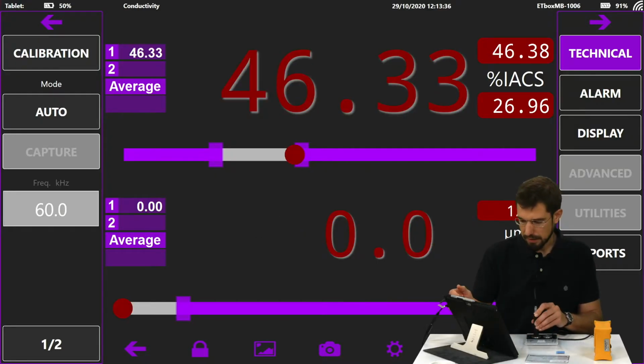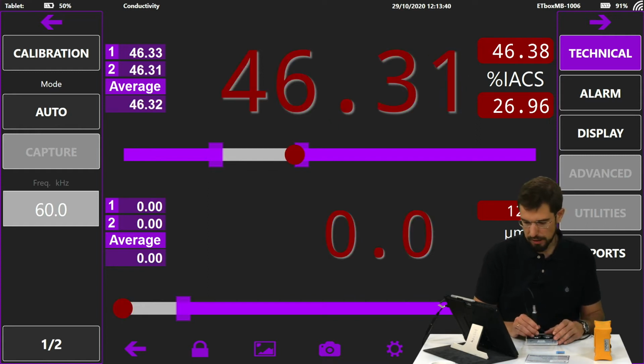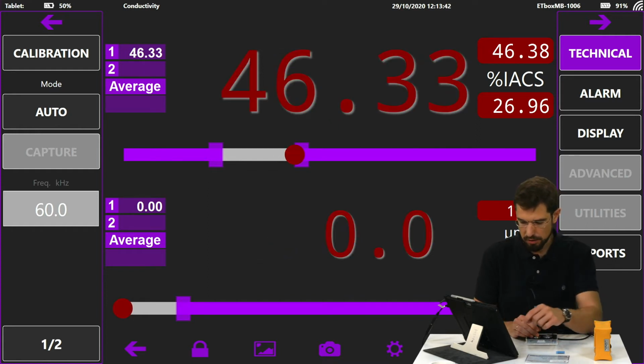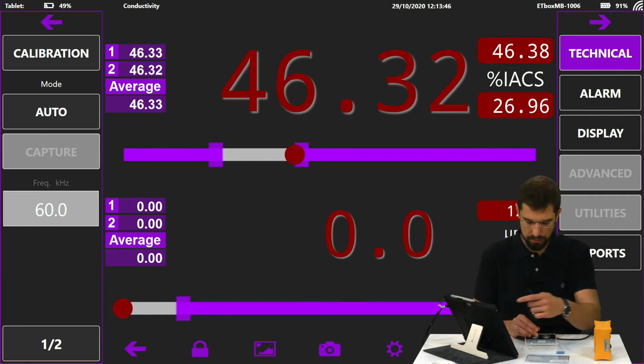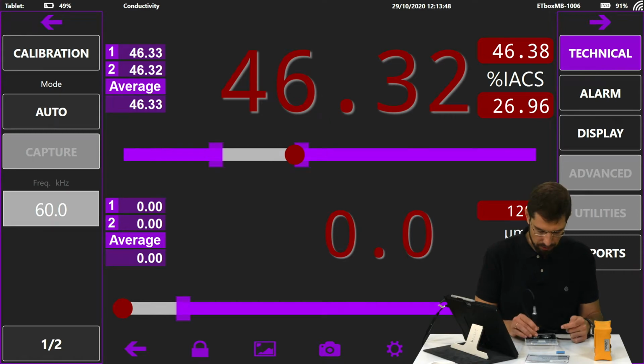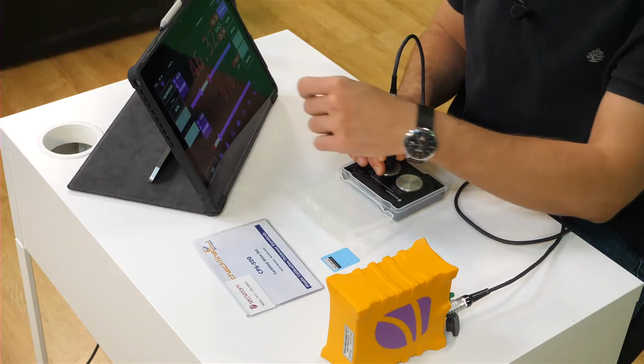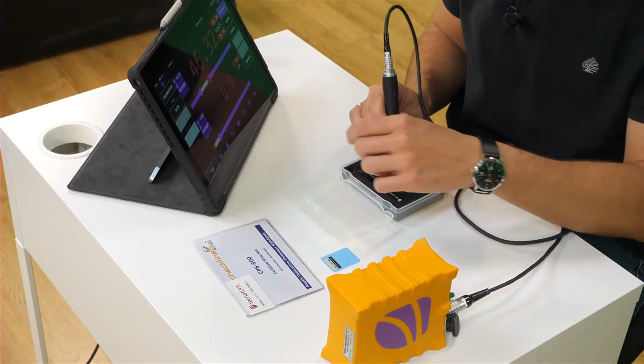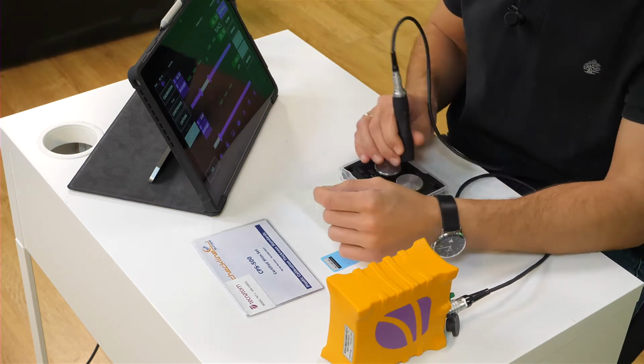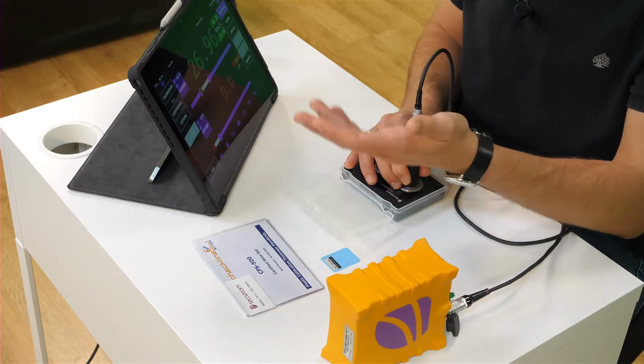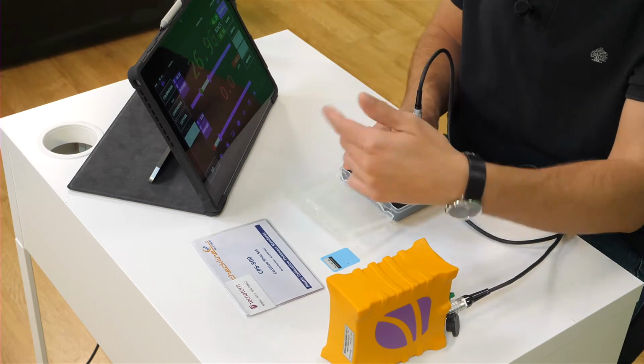On the Technical tab, we find a description of a series of parameters we can choose. That would be the acquisition mode, which is in this case automatic, and the software identifies if the probe is on the air or if it's laid on the material. When the measurement is fixed, it goes blue. If we set it to continuous, this is measured non-stop. It refreshes our measurements constantly.